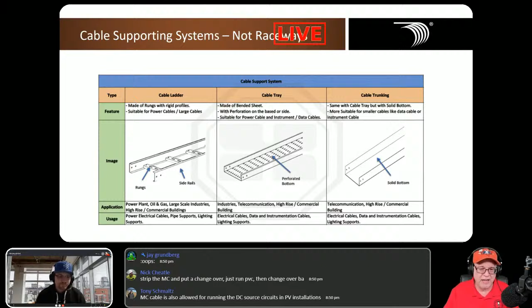I'm rapidly running out of time, but some other tidbits to think about with tray cables: the most common types of cables that go into a cable tray system are TC cables, PLTC, instrumentation tray cable, and Metal-Clad — again, very popular to put MC cable in a cable tray. MI cable, believe it or not, is used a lot as a supporting system inside of a supporting system like a cable tray. Fiber optic cables are run in cable trays all the time, as are communication cables — CMP, CMR, CMG, that's plenum rated, riser rated, or general use. It's also very common to use cable trays for fire alarm cables, non-power limited and power limited, and circuit integrity cables. All of those utilize cable trays all the time. So that's kind of a tidbit of the most important aspects of running cables in a cable tray.